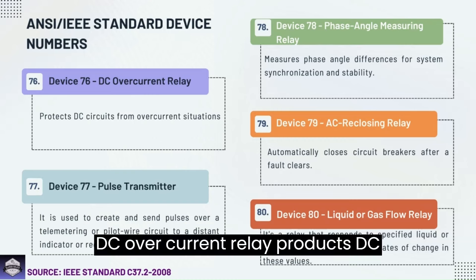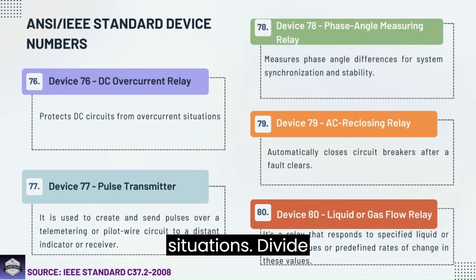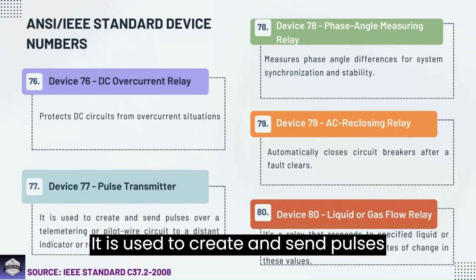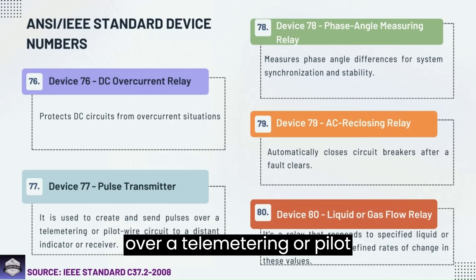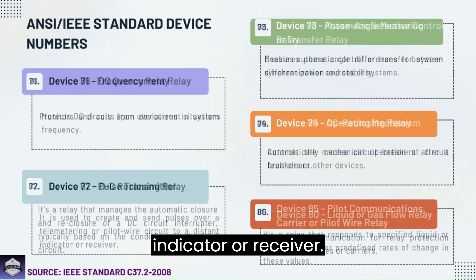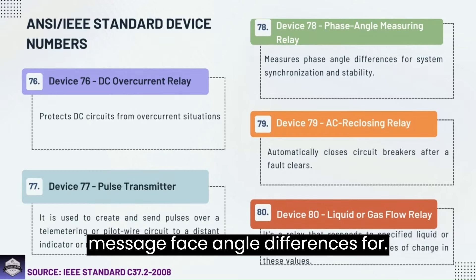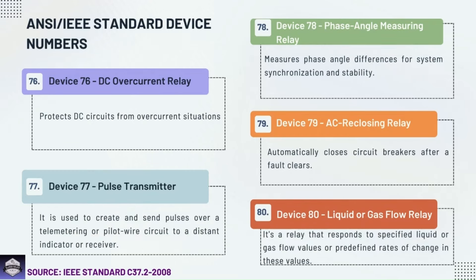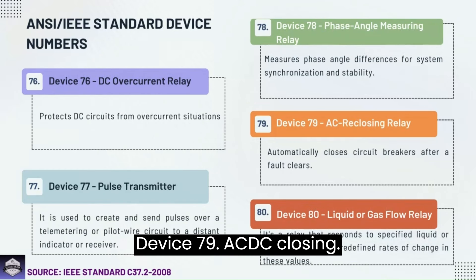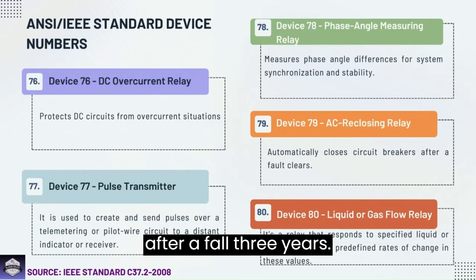Device 76: DC overcurrent relay — protects DC circuits from overcurrent situations. Device 77: Pulse transmitter — used to create and send pulses over a telemetering or pilot wire circuit to a distance indicator or receiver. Device 78: Phase angle measuring relay — measures phase angle differences for system synchronization and stability. Device 79: AC reclosing relay — automatically closes circuit breakers after a fault clears.